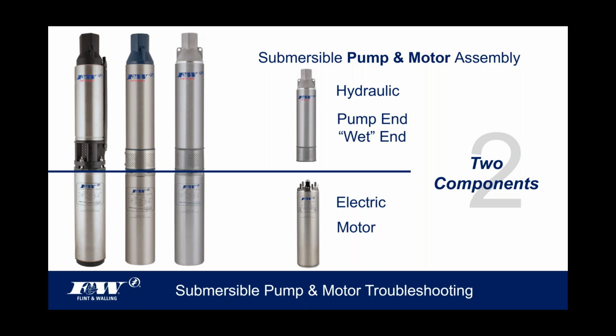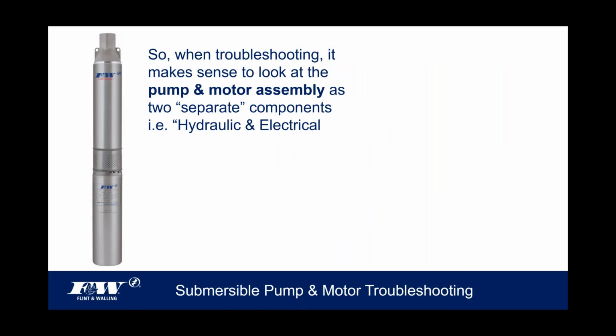When I'm attempting to troubleshoot, I look at the pump and motor assembly this way. I'm going to run through a few scenarios today, but the questions I ask early on are meant to provide me with some direction. In other words, am I going to be looking more at the hydraulic side of this, or is it going to be more motor related? So when it comes to troubleshooting, it makes sense to look at a pump and motor assembly as two separate components. You've got the hydraulics, or the pump end, on the top side. You've got the electrical, the motor, on the bottom side.